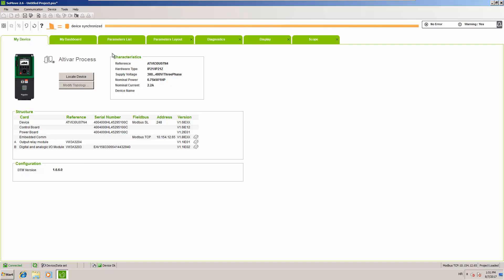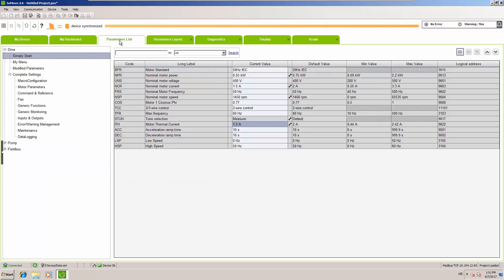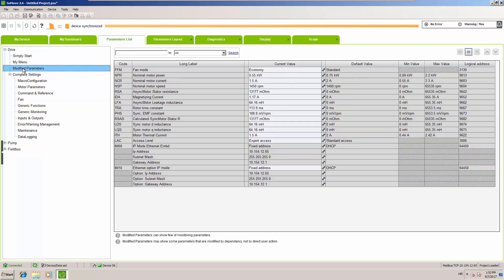Before you begin, you need to set up basic parameters for the drive. Basic parameters always include entering the proper motor nameplate data into the drive and doing an auto-tuning. Additionally, we change some fan management settings and then set up the IP address so we can easily connect to the drive and use the scope.